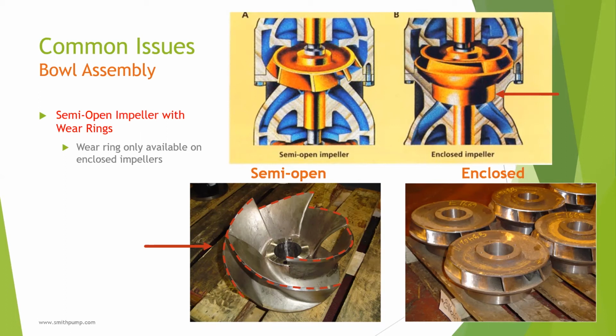Over time, this edge wears and the tolerance can open up, but it's okay because restoring the tolerance can be done from the surface without even pulling the pump. Adjusting the impeller at the motor restores the clearance back to the original tolerance and efficiency. So we recommend wear rings, but remember they're only for enclosed impellers.